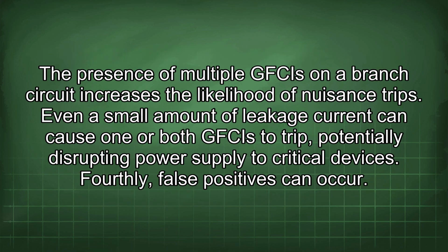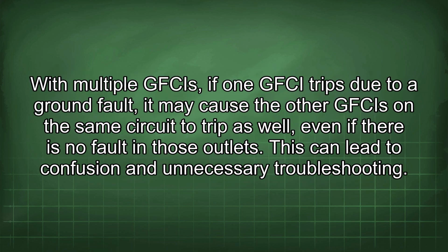The presence of multiple GFCIs on a branch circuit increases the likelihood of nuisance trips. Even a small amount of leakage current can cause one or both GFCIs to trip, potentially disrupting power supply to critical devices. Fourthly, false positives can occur. With multiple GFCIs, if one GFCI trips due to a ground fault, it may cause the other GFCIs on the same circuit to trip as well, even if there is no fault in those outlets. This can lead to confusion and unnecessary troubleshooting.